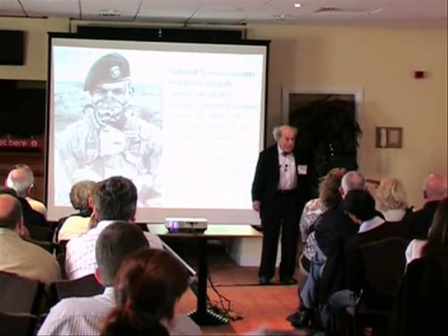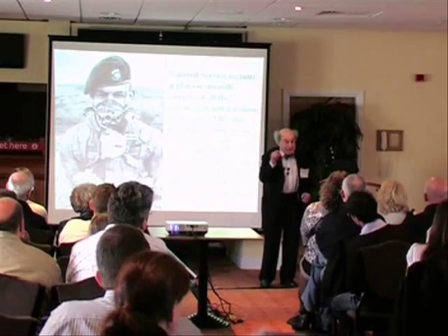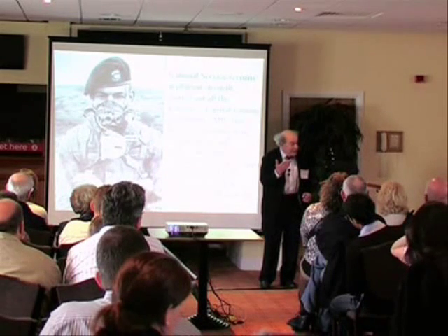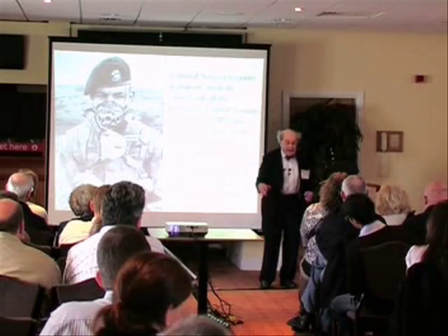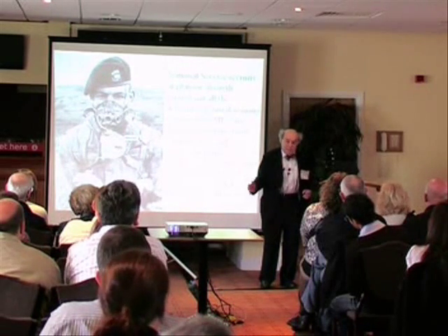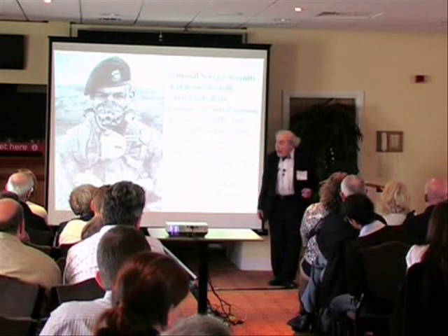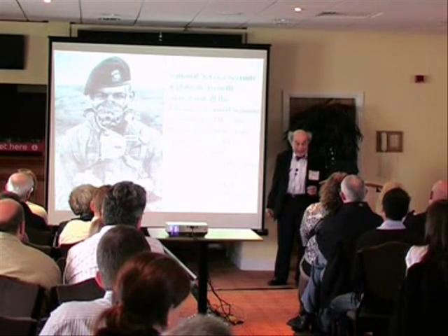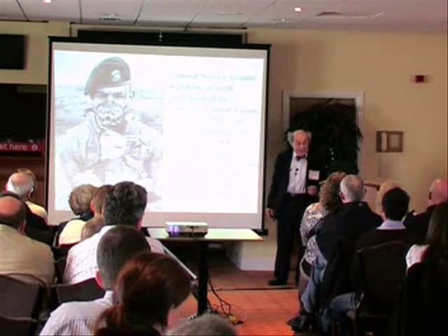They told me about this during my education, and I spent most of my last year at college devising a machine for doing this — it was called the IMP. What it did was measure the amount of air which the subject expired and also take a statistical sample of it. There was a little pump inside the machine which took one ten-thousandths of the volume, modulated by how much air was passing through, and it accumulated all this in a neoprene bag, which isn't very permeable to carbon dioxide and oxygen. Many hundreds of soldiers all over the country did their first ten weeks of training wearing one of these machines — even sleeping with them.